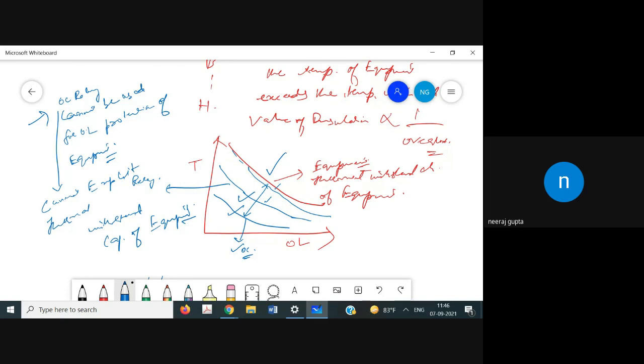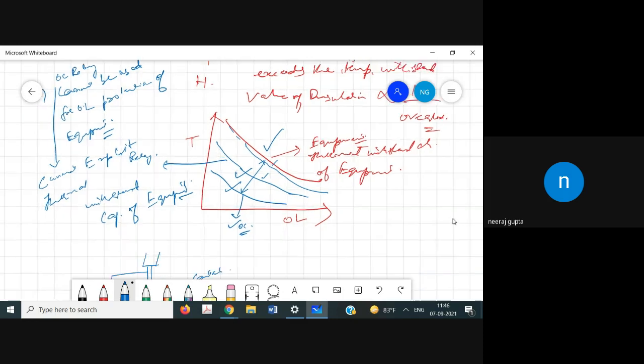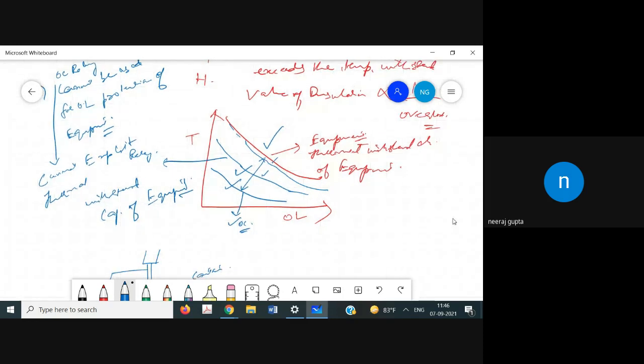And you can say the overcurrent relay, why the overcurrent relay cannot be used for the overload protection? It is because the principle of overcurrent relay is different. We cannot exploit the thermal characteristics in that very case of overcurrent relay, because the time in that very case is very small. उसमें time जो होता है हमारा बहुत कम होता है.